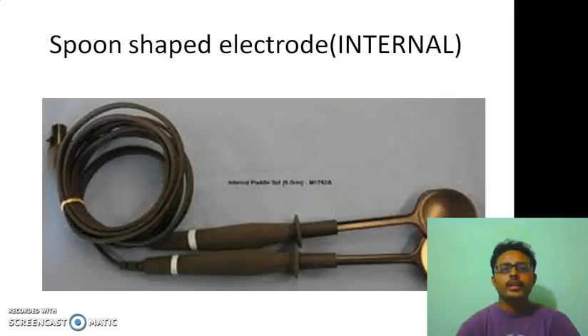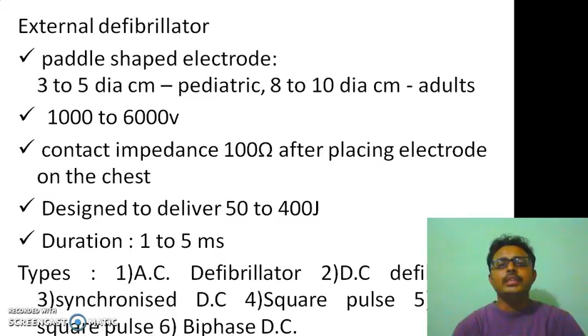The diameter will be 3 to 5, and the operating voltage will be 1000 volts to 6000 volts. The contact impedance is 100 ohms. If you compare the contact impedances, the internal is 50 ohms and the external defibrillator is 100 ohms, and the duration is 1 to 5 milliseconds. This shows the types of defibrillator: AC, DC, synchronized DC, square pulse, double square pulse, biphase DC. These are the various types of defibrillator, but widely we are using the DC defibrillator.